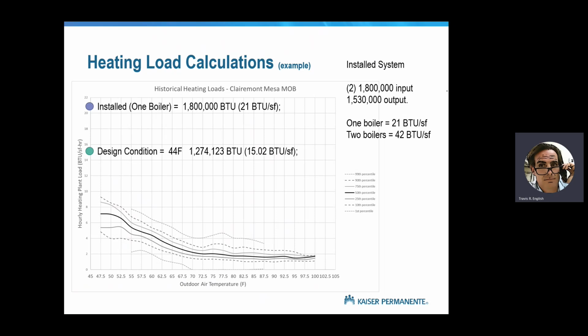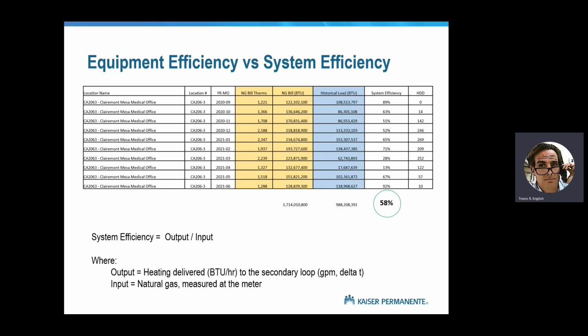Now, there's probably somebody in the room who says, well, we have boilers that do 10 to 1 turn down or 12 to 1 turn down. They're actually more efficient at the low range than they are at full load, right? Well, that would be great if that were true. So let's go ahead and check that. And we'll use the data to check that. Because when you have a data system, you can sum up the load in every hour of the system during the year.